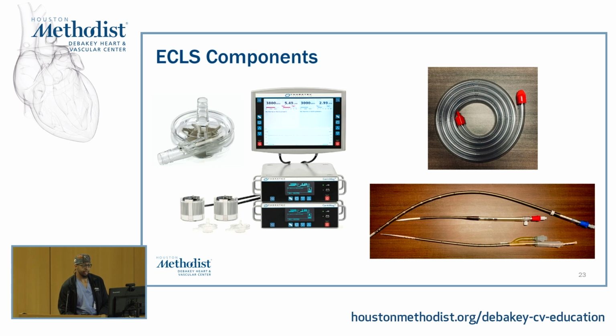Tubing, which is that clear tubing up in the upper right corner, which is usually going to be some biocompatible tubing that connects all of the components of your circuit, connect your patient's cannulas to the centrifugal head. That tubing, like I said, is biocompatible, trying to reduce the inflammatory response that will occur when you pull the patient's blood out of their body and through an extracorporeal circuit. And then, of course, you'll have your console to drive the pump as well as a motor to spin that centrifugal head.